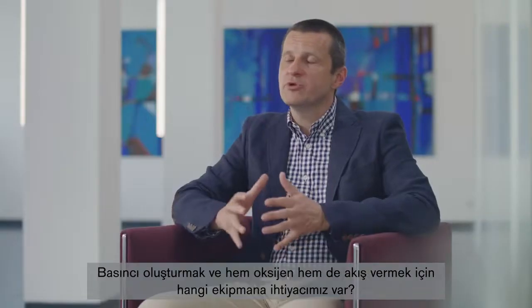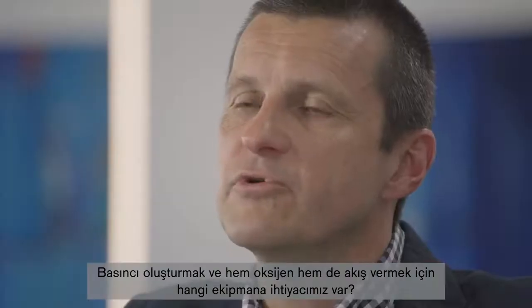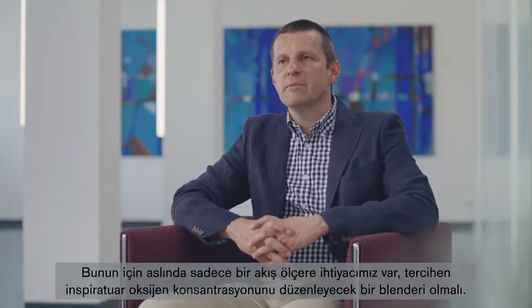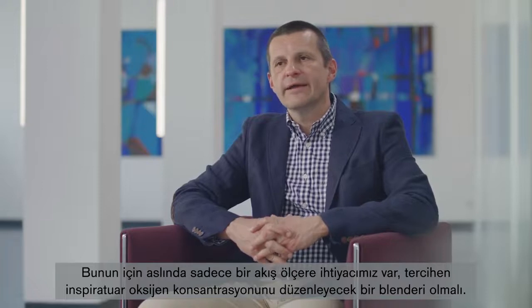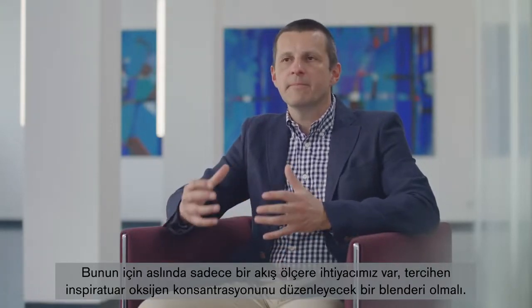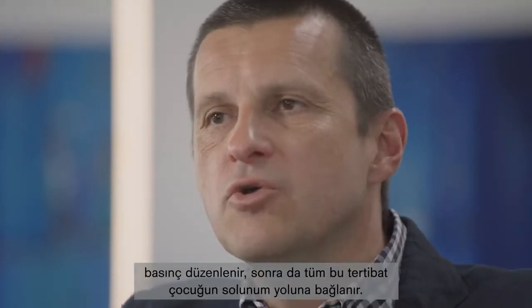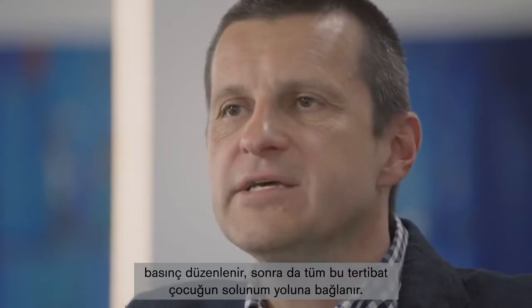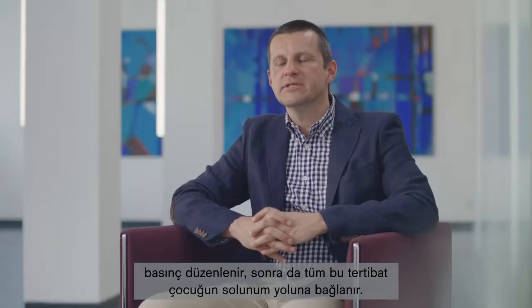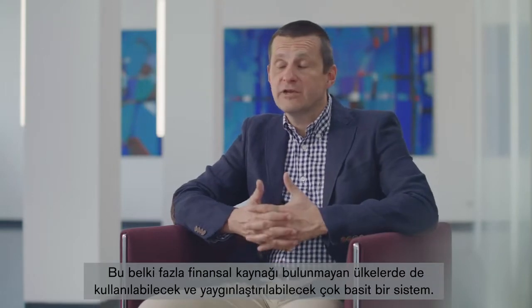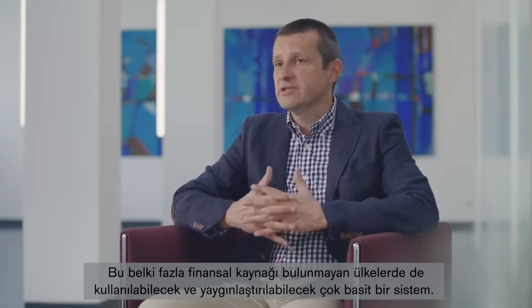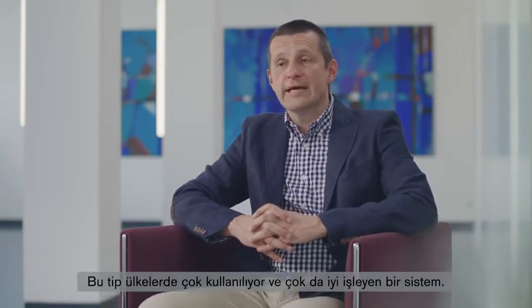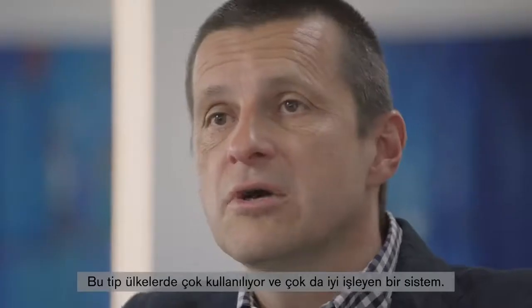What equipment do we need to generate the pressure and give both oxygen and flow? There are simple devices, such as bubble CPAP systems. For this, we actually only need a flow meter, preferably one with a blender to regulate the inspiratory oxygen concentration. The whole thing is placed into a box in which there is water, and via the immersion depth of the rod, which hangs in the water, the pressure is regulated and the whole thing is then connected to the child's respiratory tract. It is a very simple system that can also be used and exploited in countries that perhaps do not have large financial resources. There it is used a lot, and it is a system which works very well.